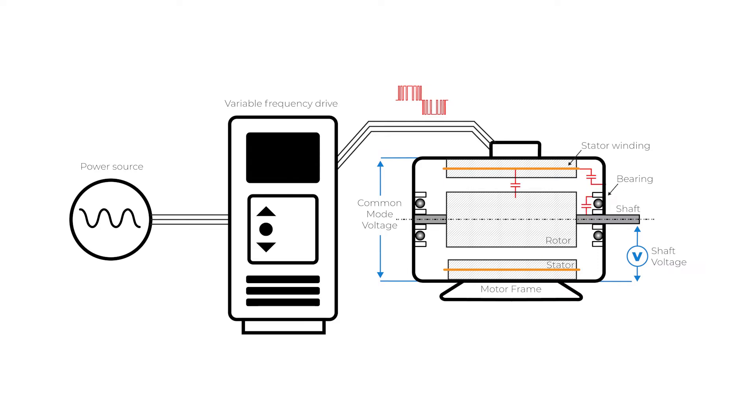Shaft voltage causes arcing through the bearing lubricant which results in pitting on the bearings and fluting on the bearing races.